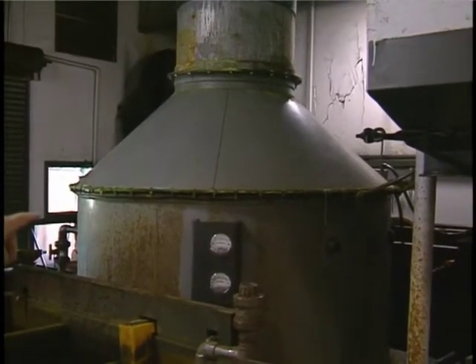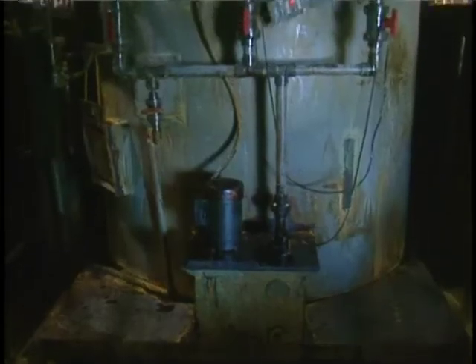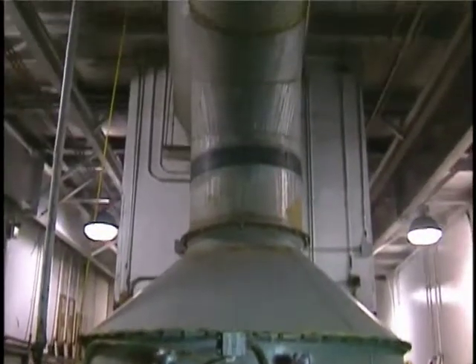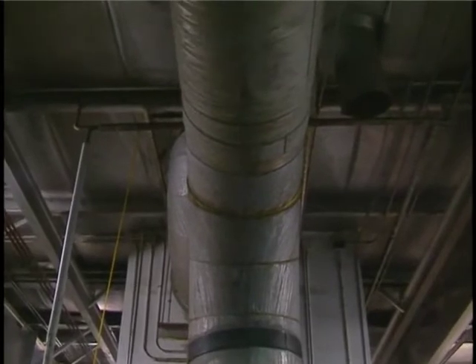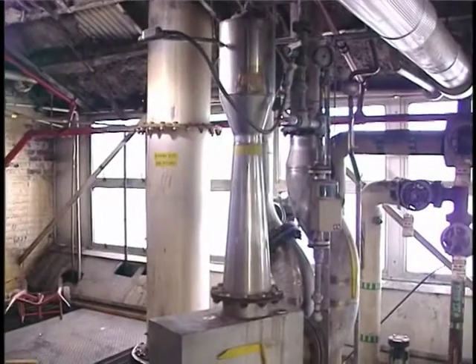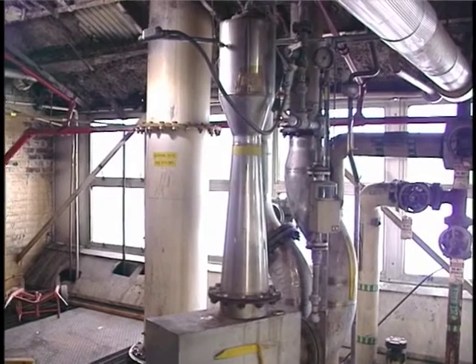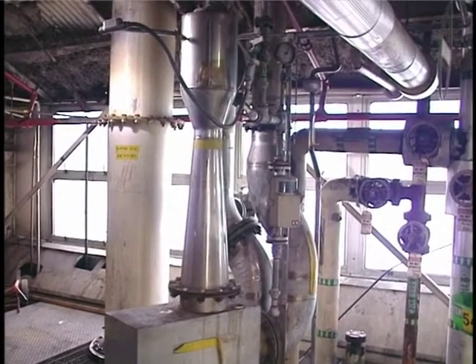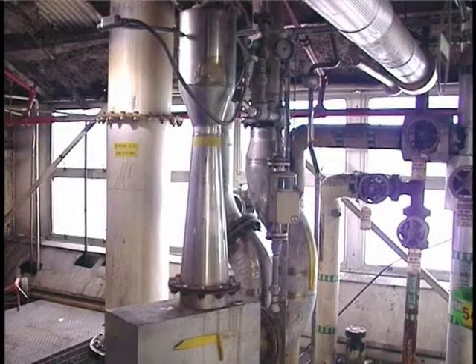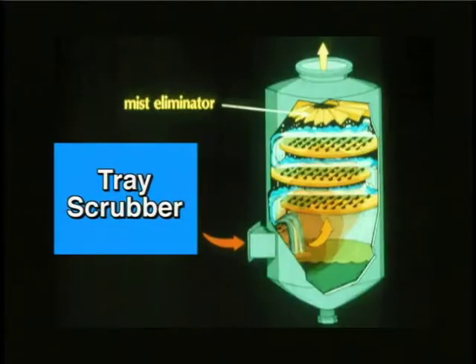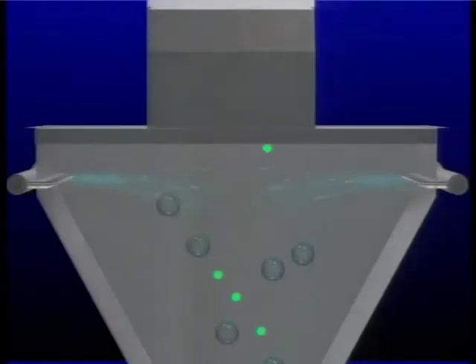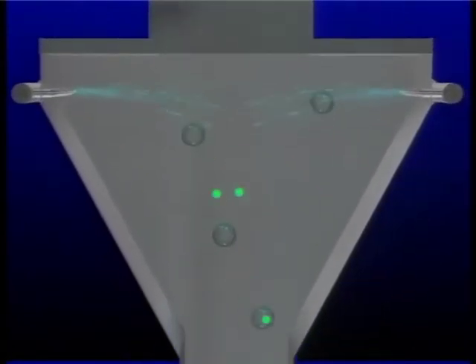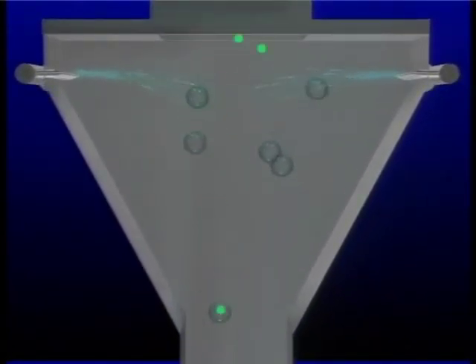Changes in scrubber pressure drop can occur for several reasons. Increased pressure drop across a packed bed or tray scrubber may indicate plugging of the bed or trays. Increased pressure drop on a venturi scrubber may be caused by increased liquid flow rate or by adjusting a variable throat damper to a more closed position. A decrease in the pressure drop across a tray scrubber may indicate warped or collapsed trays, while for a venturi scrubber it may be caused by decreased liquid flow rate or by adjusting a variable throat damper to a more open position.